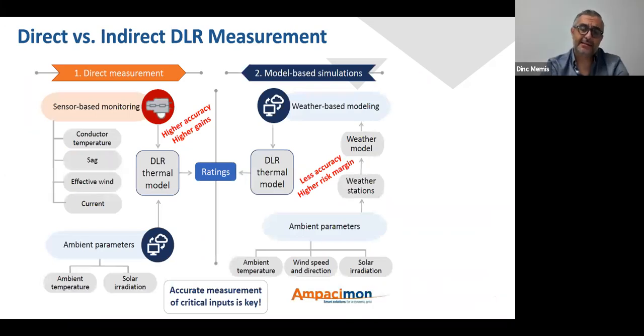This slide is quite a busy slide. I am not going to take you through it, but it provides a bit more insight regarding the process and also a comparison between the two methodologies: direct measurement through sensor-based monitoring versus indirect measurement through model-based simulations. The bottom line is that sensor-based real-time monitoring and measurement is a proven DLR technology, providing real-time, higher accuracy and higher gains in the capacity of the existing line.